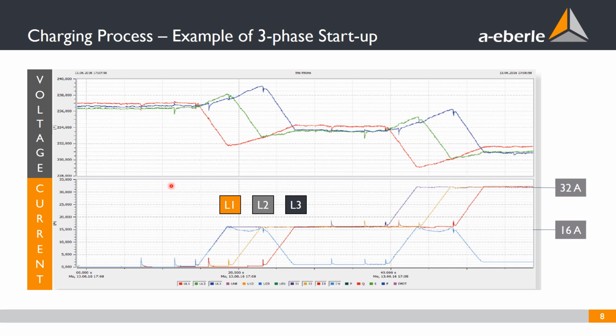You can see here that at the end of the startup process, the device is going to charge with 32 amps, 22 kilowatts. But it's not switching on directly from 0 amps to the full power. It's cascading the charging process from line 1 to line 2 to line 3. First to a stage of 16 amps, and after about 10 seconds, they go for the second stage at 32 amps. This is a little bit more friendly to the grid because you do not have this high current peak and you're not producing as many transients as you would with a direct switch-on.